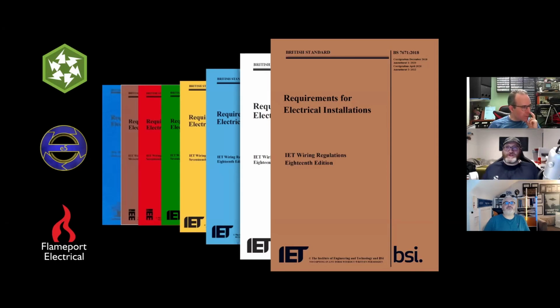A couple more questions. Peter says, come across a property with plastic coated metal pipes for an oil boiler, right? Yeah, plastic coated metal pipes. You need to be careful with those because it depends whether they're extraneous or not, because some oil tanks are made of plastic, in which case very unlikely to be bringing potential in. Of course, some oil tanks are made of metal and they sit on the floor. So yes, it will. If you're going to bond oil pipes, you can't use the standard 951 clamp because they don't go down to the small diameter. So you have to get special small ones. And of course, you need to remove a part of the plastic coating.